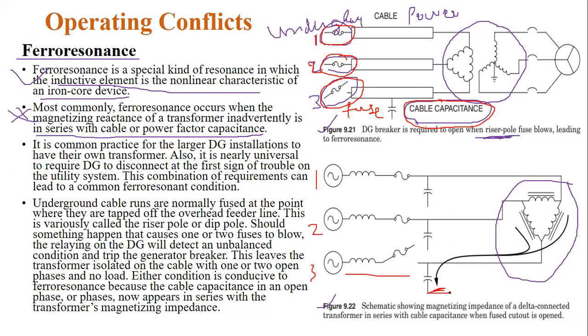Now see this grounding capacitance or cable capacitance. You can see this capacitance. That may lead to the rise of some resonance with some inductance in the system, which will lead to the resonance. This is one of the cases where resonance occurred in the system. Do you understand that? So this is the underground cable.